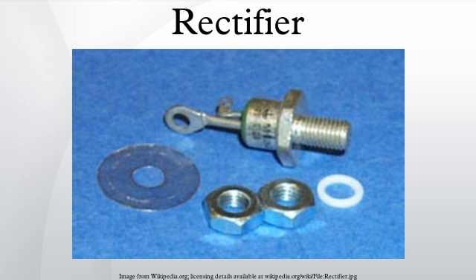Synchronous rectifier. To convert alternating into direct current in electric locomotives, a synchronous rectifier may be used. It consists of a synchronous motor driving a set of heavy-duty electrical contacts. The motor spins in time with the AC frequency and periodically reverses the connections to the load at an instant when the sinusoidal current goes through a zero crossing. The contacts do not have to switch a large current, but they must be able to carry a large current to supply the locomotive's DC traction motors.